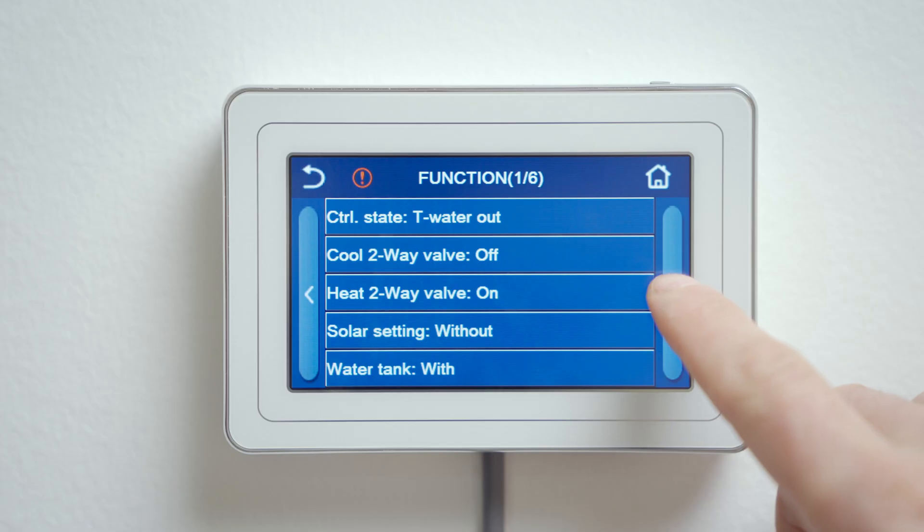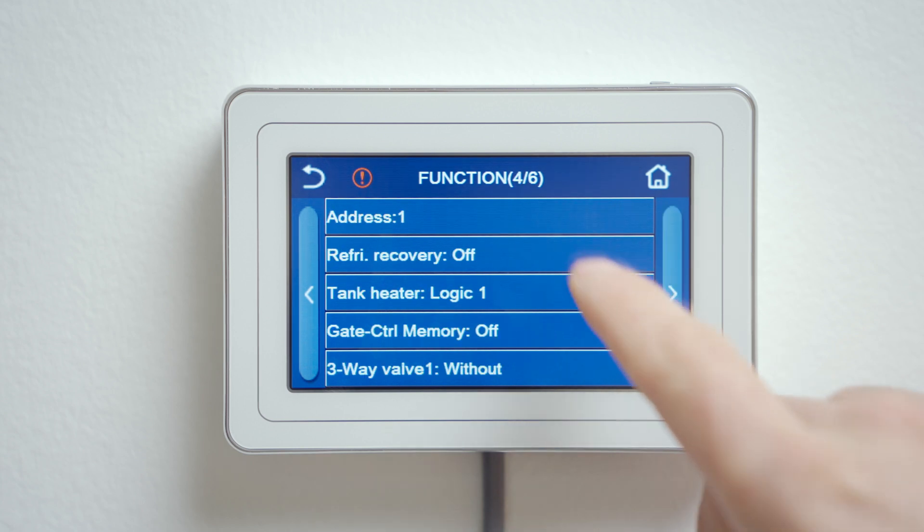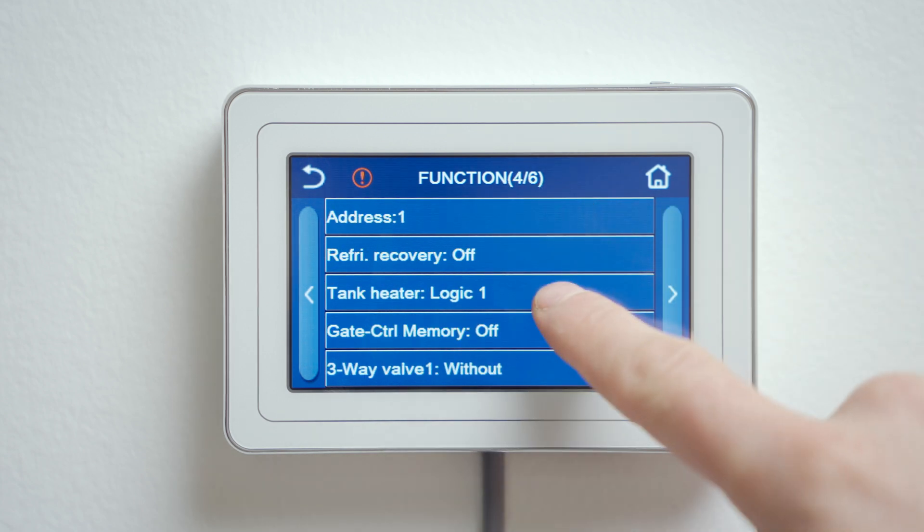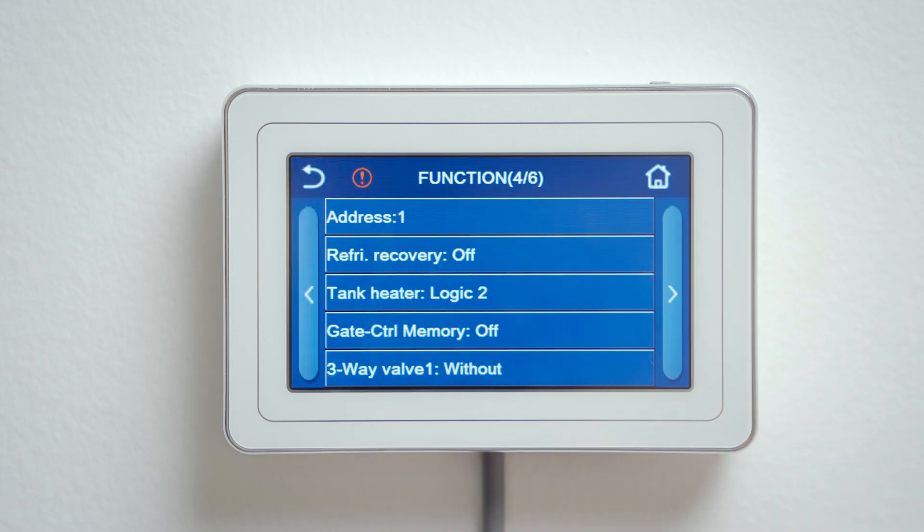When the heat pump is used also for heating domestic hot water, it's recommended to have an electric heating element in the tank for disinfection and possible emergency mode. Whether the heating element is present in the domestic hot water tank or not, it needs to be set. On the fourth page, click on tank heater and select logic number two. If you don't have a domestic hot water tank, an A appears.